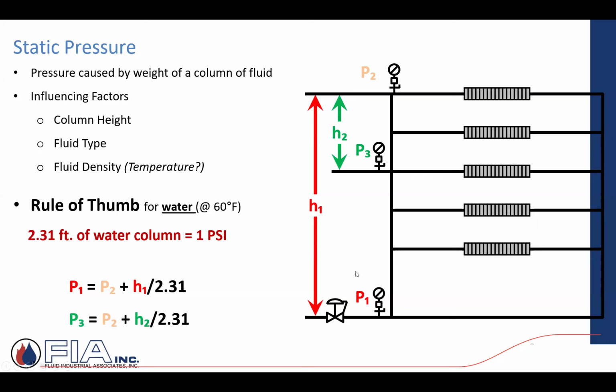What does it mean? Well, in this case, what it's saying is, what's the physical height in feet? That height divided by 2.31. And if you have positive pressure at that high point, that would be represented by P2. Add those two together, and that's what that gauge P1 would be displaying. So the physical height divided by 2.31 plus any positive pressure at that high point, that's what P1 should be reflecting, should display.